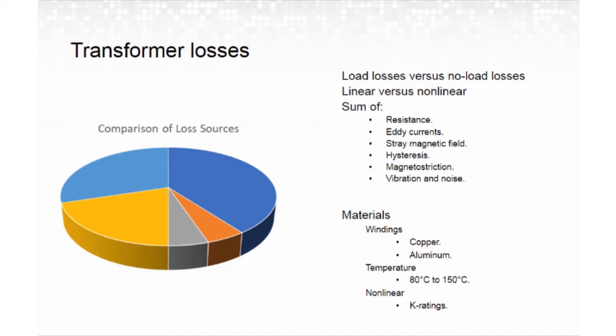Now, energy losses within a transformer come from several sources. Losses inherent to any transformer may be load dependent or load independent, which is also known as core losses. The pie chart shown is not labeled because percentages of each type of loss will depend on the transformer loading and the material selection. Load losses are going to increase as current through the windings increase. Other losses are called core losses, and they are constant regardless of the transformer loading, and they essentially exist anytime a transformer is energized.